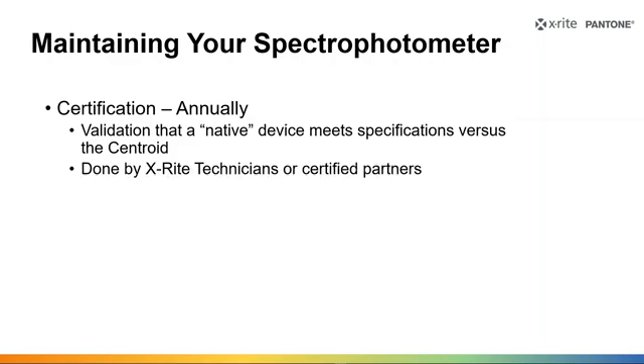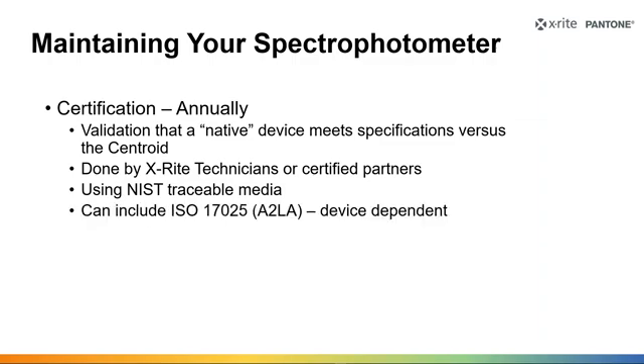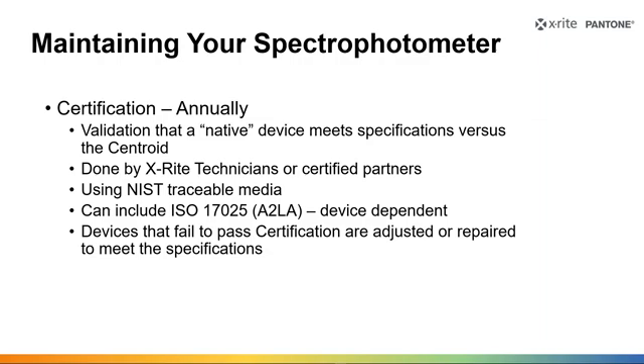It's done by X-Rite technicians, or we have some certified partners that can do it. We're using NIST traceable media, so the color standards that we're using are traceable back to NIST. It can even include ISO 17025, sometimes called A2LA certification. That's dependent on the different types of devices. We can do that for many of our devices. Some don't qualify. But what we're doing is making sure that your instrument natively measures the way it's supposed to measure. Okay? And if that device fails to pass certification, then we need to adjust it, or potentially, if adjustment won't get it there, we may have to repair something so that that device will meet the specification.